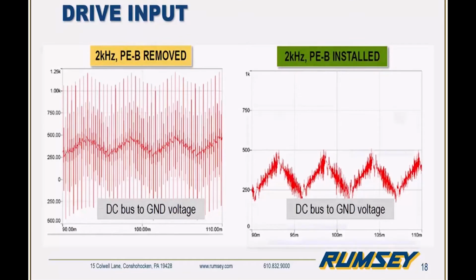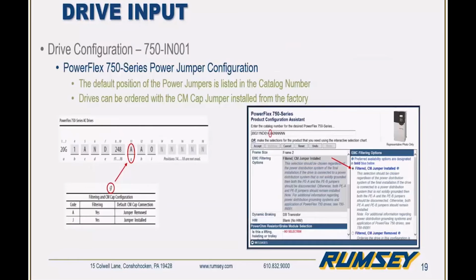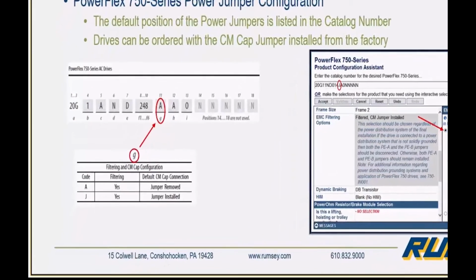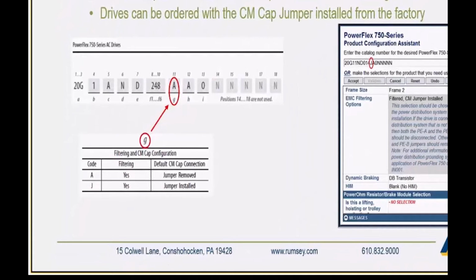So another thing to note on the PowerFlex 750 series, we were referencing and talking about the position of the power jumpers. It's actually possible to determine basically the way the drive is configured from the factory by looking at the catalog number. On the left-hand side here, we see the catalog string, and based on its configuration, we can see if the jumper is installed or removed by default from the factory.